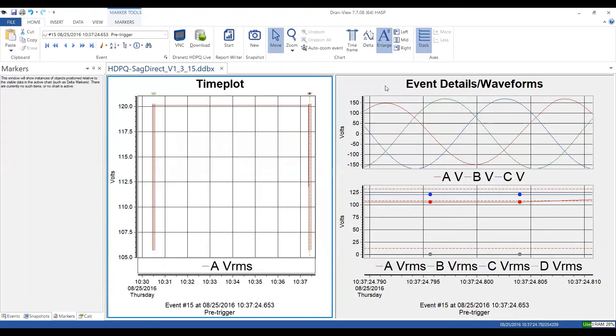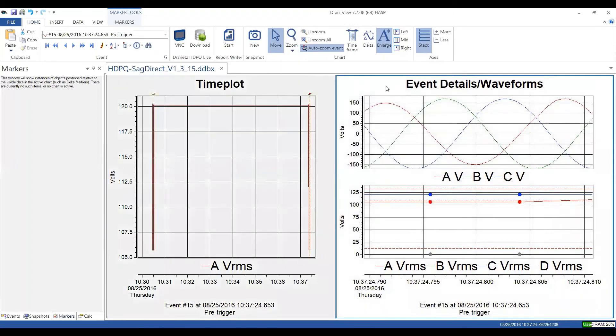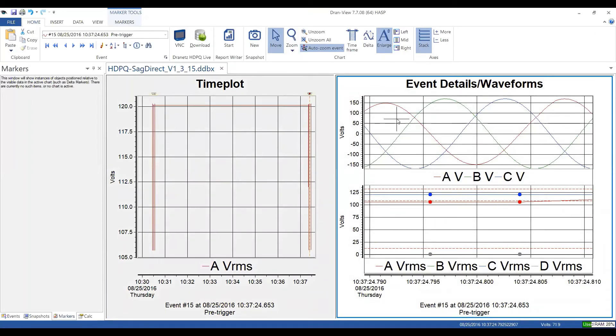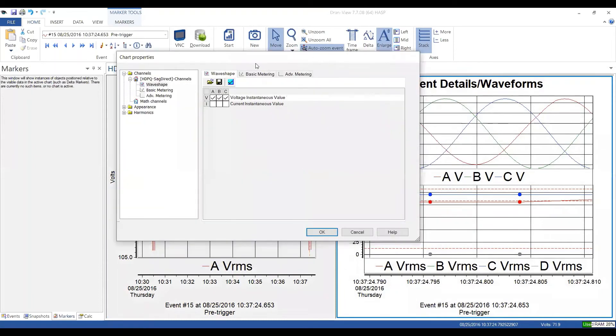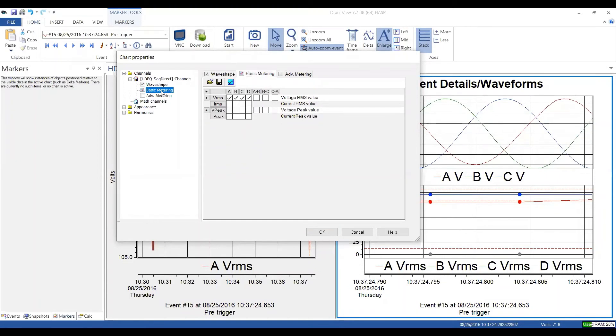So when I go on the right-hand side, I have the ability to look at the details of what's displayed for events. So this is very important. So when the HDPQ family and even its generation before it, the PX5 family, when it records an event, it has the ability to both record the wave shape and the trends of the event. And that's displayed up on the top and the bottom over here.